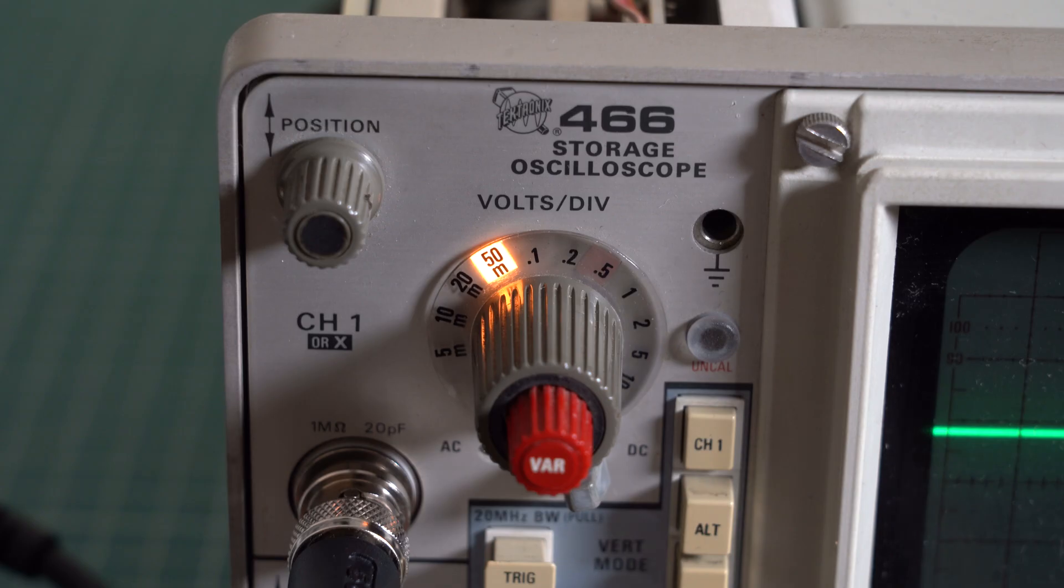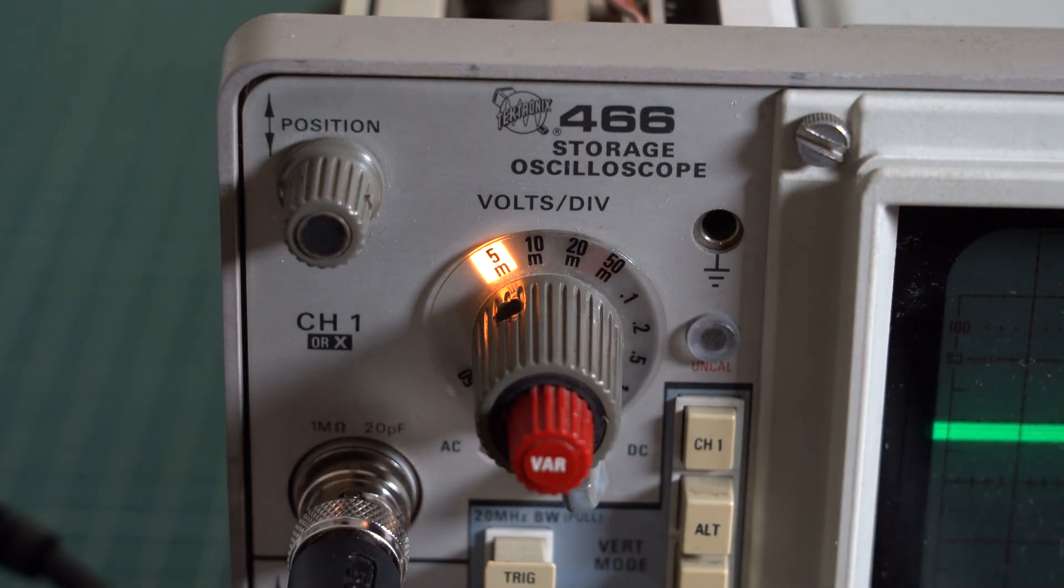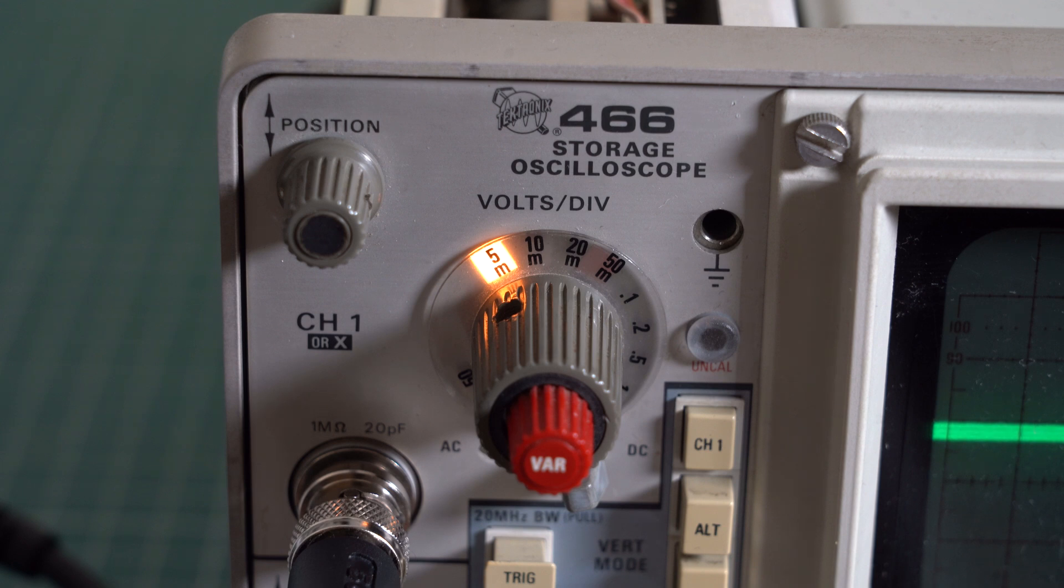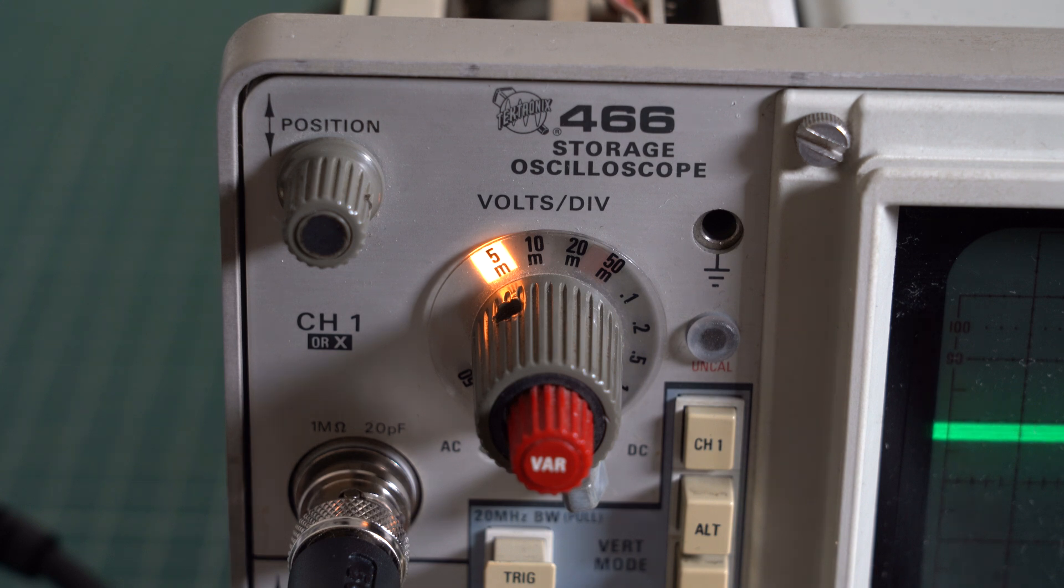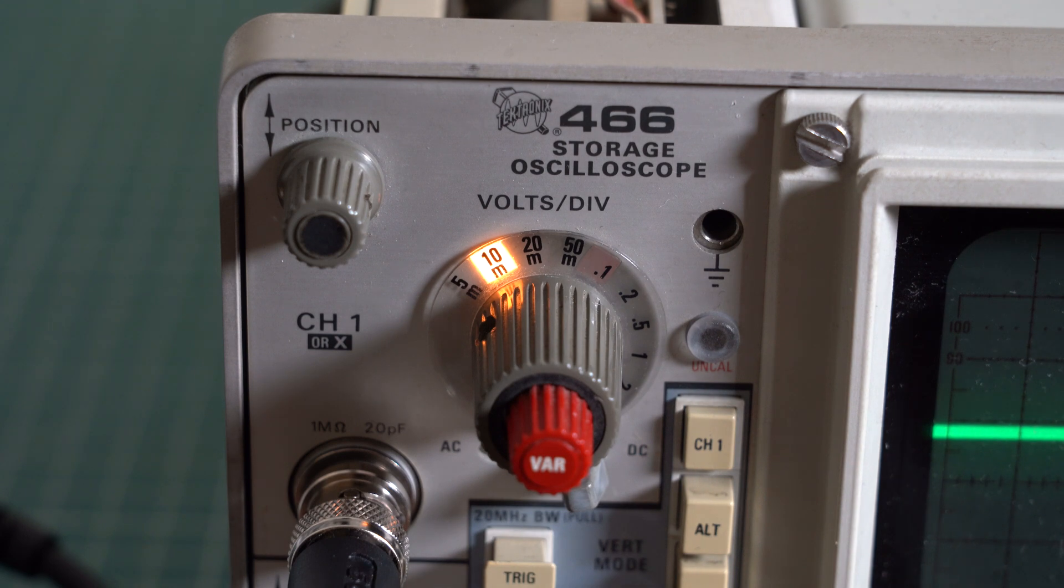Basically how this works is that if you set the sensitivity to 5 millivolts then you're going straight into the vertical preamp. So basically you bypass the attenuator. This 5 millivolts per division is the native sensitivity of the circuit. And if you want to decrease the sensitivity by going to a higher number you have to add some attenuation.